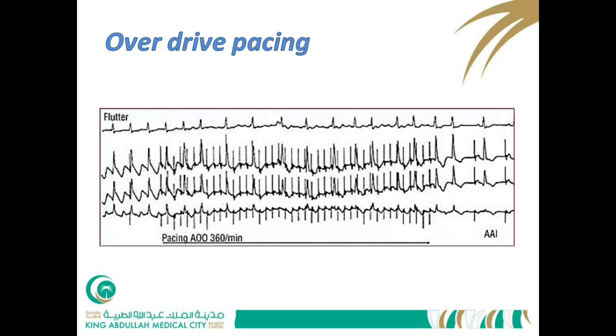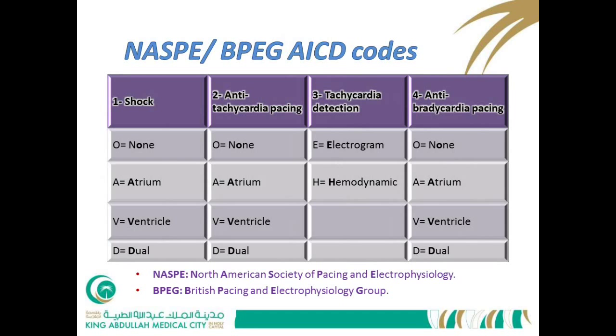The AICD also has its own code. The first position is the shock chamber — atrial, ventricular, or dual. The second is anti-tachycardia pacing — atrial, ventricular, or both. The third is tachycardia detection — by ECG analysis or hemodynamic changes such as metabolic variance or blood pressure. The fourth is anti-bradycardia pacing, as most AICDs have an integrated pacemaker enabling them to pace the atrium, ventricle, or both.